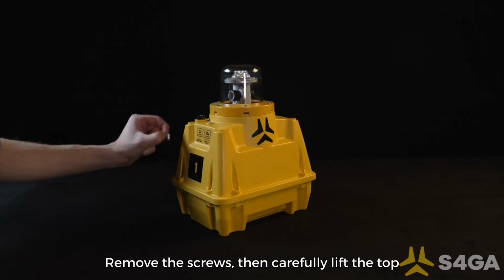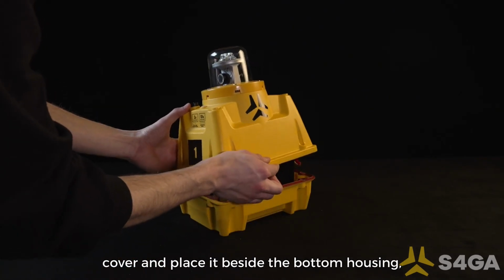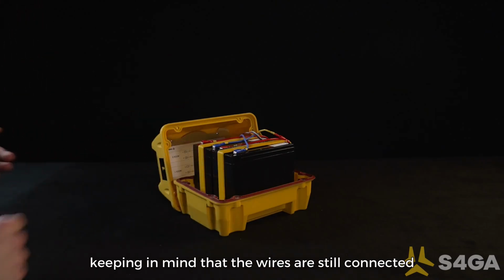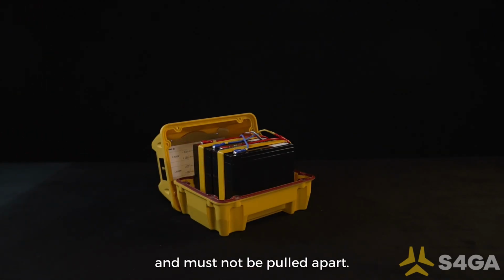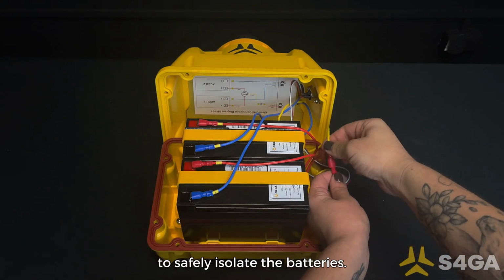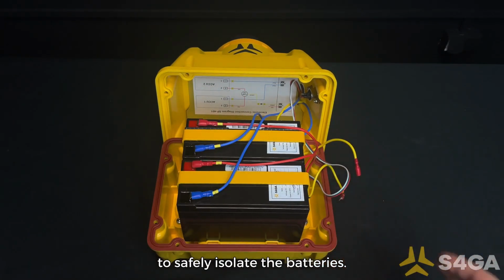Remove the screws, then carefully lift the top cover and place it beside the bottom housing, keeping in mind that the wires are still connected and must not be pulled apart. Disconnect the yellow fuse cable to safely isolate the batteries.